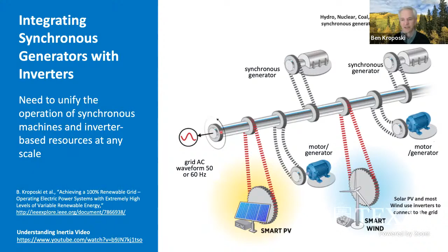And there is a big need right now to think about how we unify the operation of both synchronous generator technology and inverter-based technology like photovoltaics and wind turbines in such a way that they can be integrated at any levels and at any scales. A lot of this has to do with the fact that if we start to reduce synchronous generators, say from a coal-fired power plant, and replace that with wind turbines and solar arrays, we want to make sure that we can maintain operational stability through the inertial constants in the power grid.